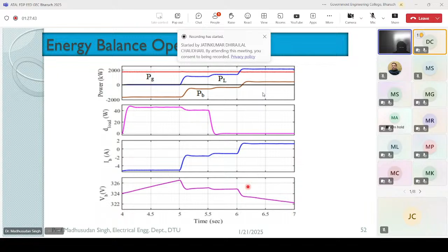Battery charging and discharging currents are also shown here, and the battery voltage profile. So the deviation of battery voltage, you see, is not much. It's just 2-3 volt deviations. This is the enlarged version of the waveform shown, just to ensure that even when the load change occurs, the DC link is well maintained. So this is just the nature of power balance in this microgrid, which is supported with wind-based generation.